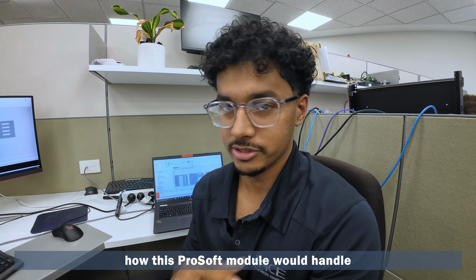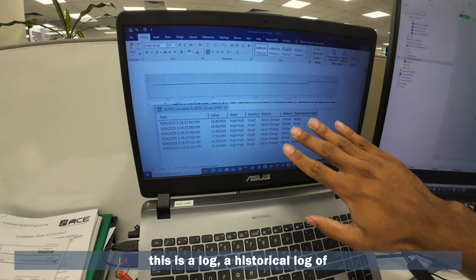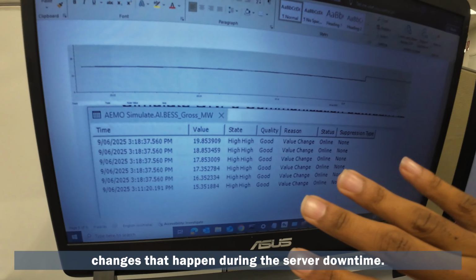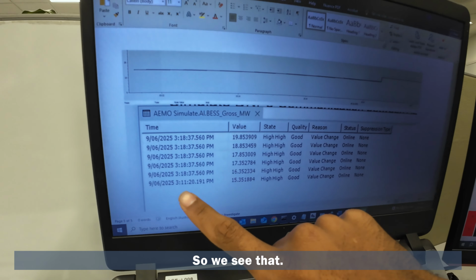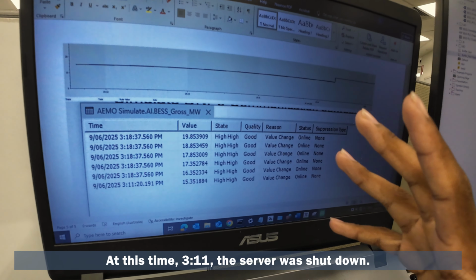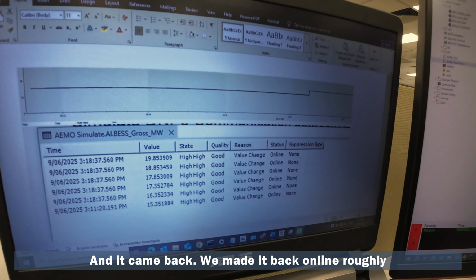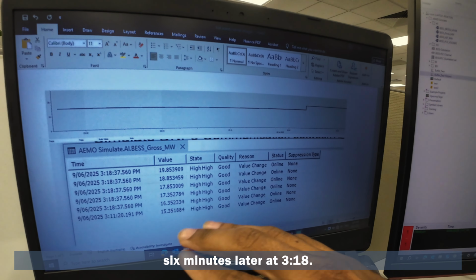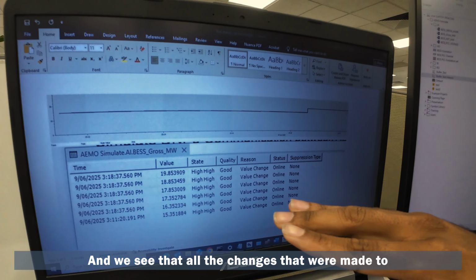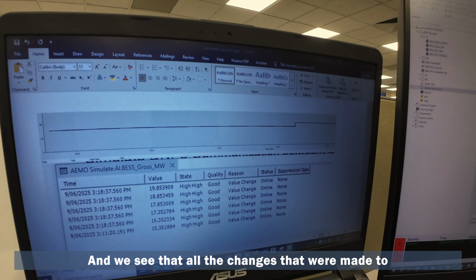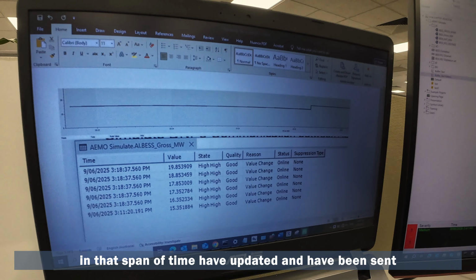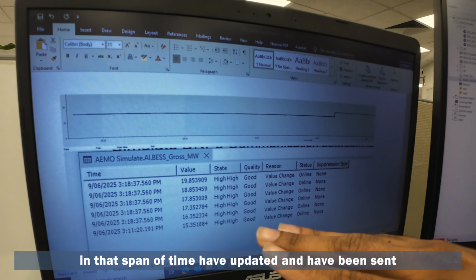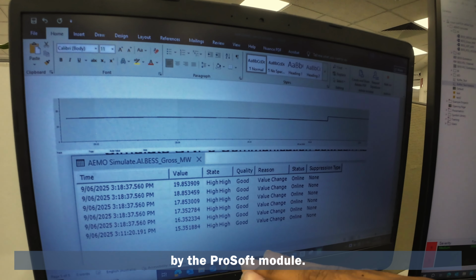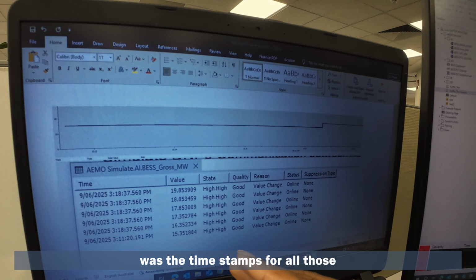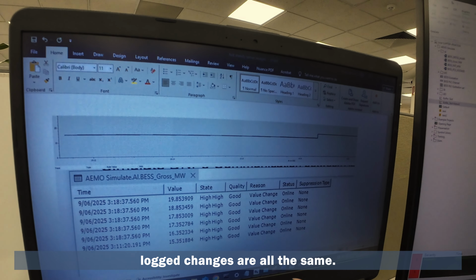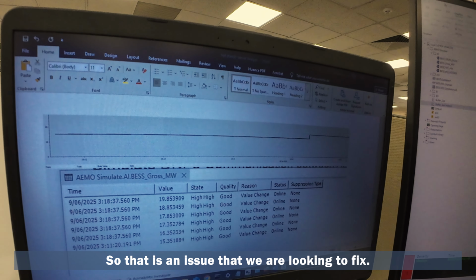What we found was, looking at this historical log of changes during the server downtime: at 3:11 the server was shut down, and it came back online roughly 5-6 minutes later at 3:18. All the changes made to those points during that span of time updated and were sent over by the ProSoft module. The only issue was that the timestamps for all those log changes were all the same, which is something we're looking to fix.